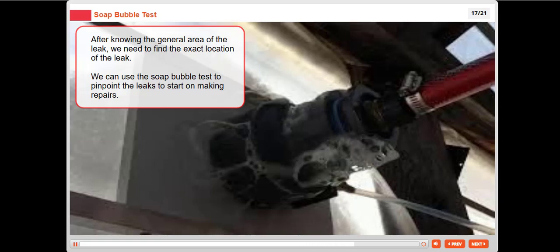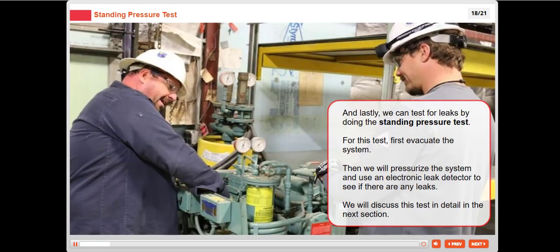And lastly, we can test for leaks by doing the standing pressure test. For this test, first evacuate the system. Then we will pressurize the system and use an electronic leak detector to see if there are any leaks. We will discuss this test in detail in the next section.